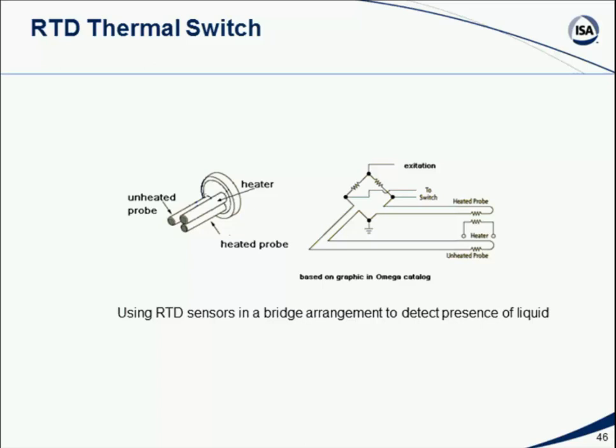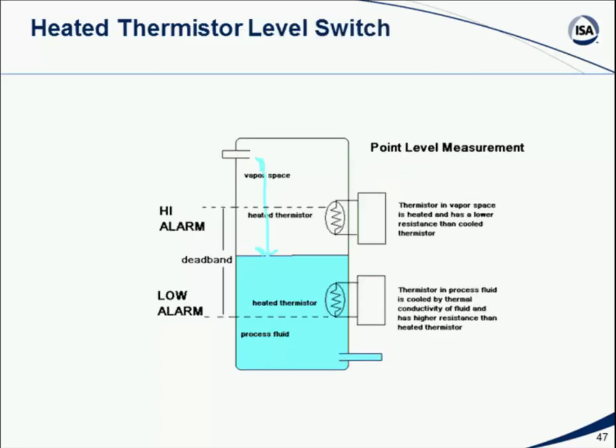Now, if this whole probe is sitting here in air or gas, whatever, air or other gases do not have enough thermal conduction to carry heat from the heater to the unheated probe and bring it up to the same temperature as the heated probe. On the other hand, once this probe is submerged in liquid, the liquid will act as a reasonably good conductor of heat, and we'll start noticing the unheated probe's temperature will rise because it's being heated by the heater. And if we wire this into a Wheatstone bridge, we can make a temperature measurement calculation here, and we can determine that, in fact, the fluid level in the tank has apparently now risen to and is at least or above the point of this probe. So if we put several of these probes into a tank, we can tell as the fluid level reaches and goes above or drops below any of these probes by the change in resistance. Again, these are point measurement devices.